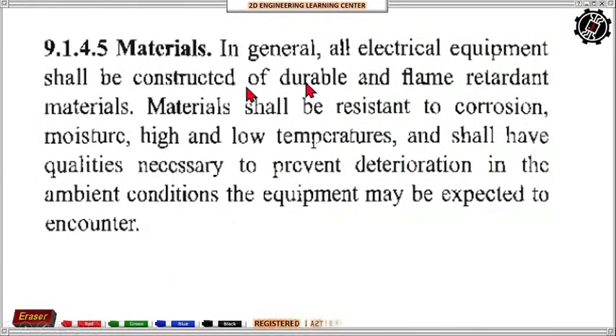In general, all electrical equipment shall be constructed of durable flame retardant materials. Additionally, the materials shall be resistant to corrosion, moisture, high and low temperatures, and shall have qualities to prevent deterioration in the ambient conditions the equipment may be expected to encounter. So for example, if our ship or watercraft is expected to go to kunyari sa mga malalamig na lugar, tapos palalayag din papunta sa mainit na lugar, so our materials, no, the equipment, the piping, no, the wires must be able to withstand the sudden change in temperature. So yan yung ibig sabihin ng ambient conditions.